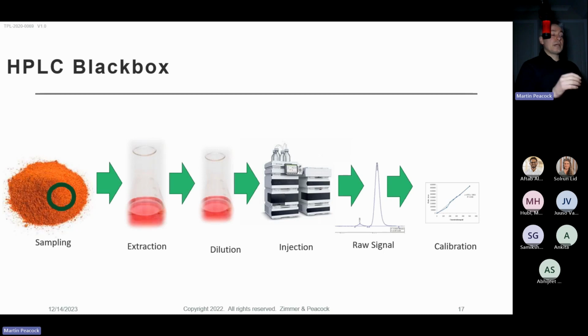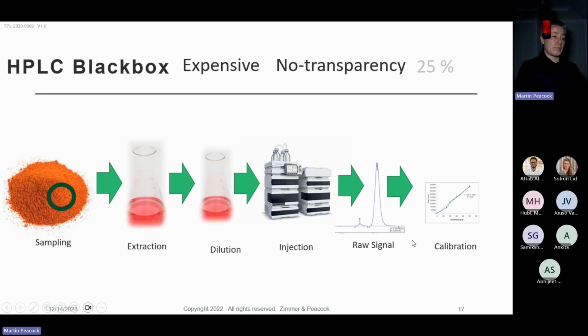And so if you get a test that was done just after the calibration, yeah, I would agree that would be the most accurate. But if you do have a test that was done a week after the system was calibrated, then in fact the sensitivity of the entire equipment has shifted, and the calibration is no longer so valid. So this means that you are paying a lot for something which is a bit of a black box to you, but I've just tried to lift off some of the layers of what's actually going on there. It's not transparent, so you don't see the raw signal, and you certainly don't understand the accuracy of their calibration.